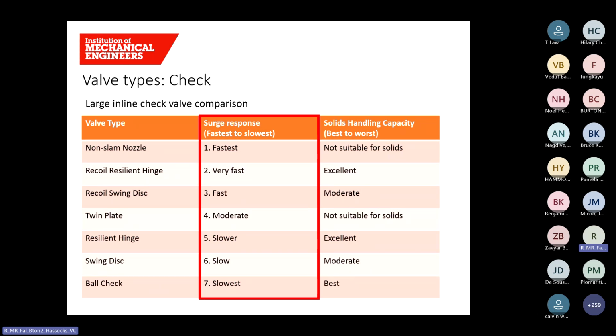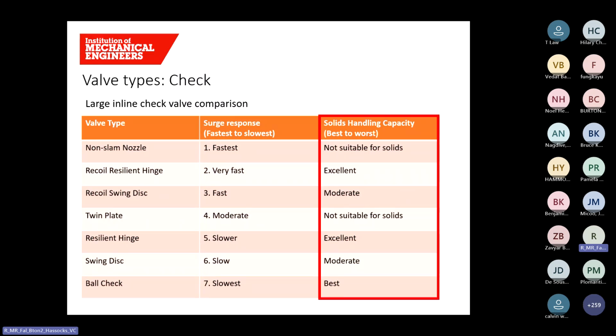You then have the options like twin plate, resilient hinge and swing discs, while the ball check valve is the slowest to react. For applications involving solids, the ball check valve excels, offering the best capability. Resilient hinge and recoil resilient hinge types also perform well, with swing disc and recoil swing disc offering moderate capability. The non-slam nozzle and twin plate valve designs are unsuitable for media with solids. Choosing the right valve depends on the specific demands of your system.